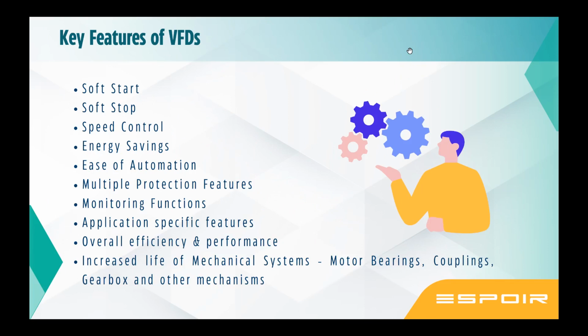Is it only for speed control? No. There are various other advantages of a VFD. The key features of a VFD, I've just put as bullets. It is soft start. The major aspect of a VFD is that it gives you a smooth start and smooth stop function. Speed control, energy saving, ease of automation. That is the key of a VFD. Ease of automation: you can change the speed, at the same time you can change the direction, you can introduce a step speed, you can inch. You can do many other aspects of automation without physically doing anything.